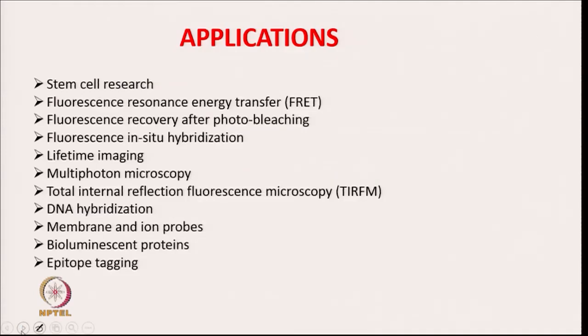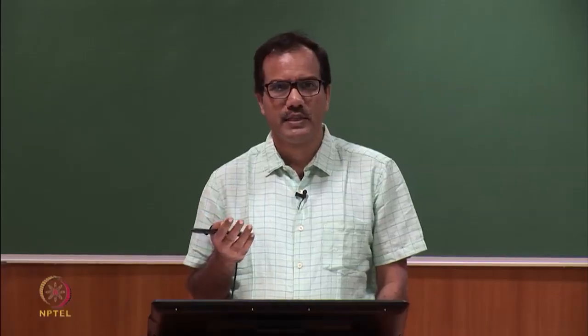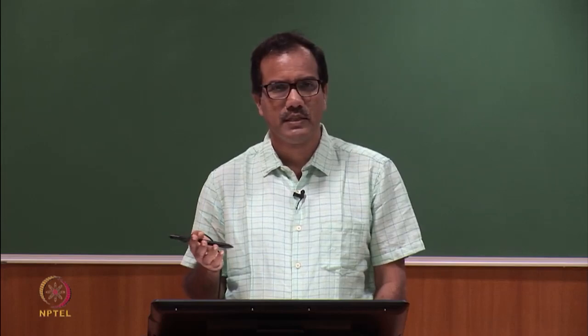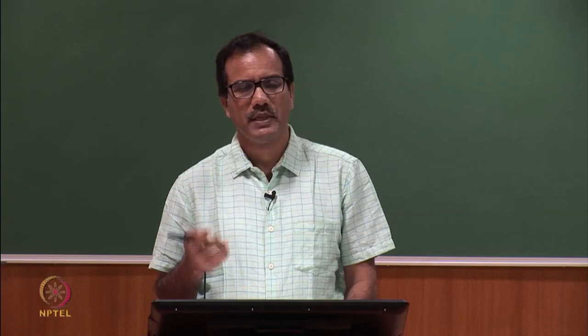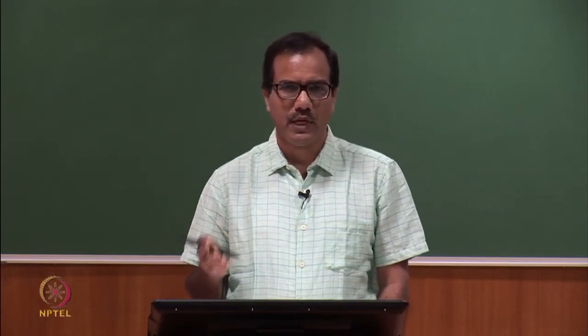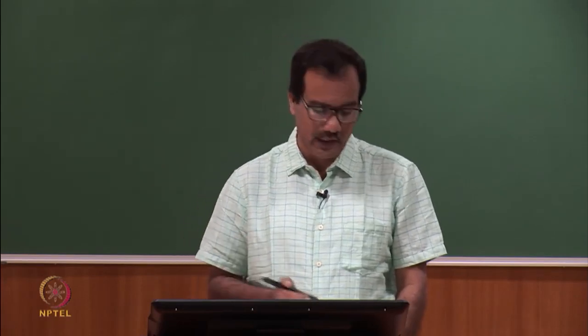In confocal microscopy, a laser light is focused onto a fluorescent specimen through the objective lens. The mixture of reflected and emitted light is captured by the same objective and sent to a dichroic mirror. The reflected light is deviated by the mirror while the emitted fluorescent light passes through the confocal aperture to reduce out-of-focus light; the focused light then passes through an emission filter to the photomultiplier tube. To generate an entire image, the single point is scanned in an XY manner as the laser focus is moved over the specimen. There are many applications of confocal microscopy including stem cell research, FRET interaction studies, fluorescence recovery after photobleaching, in-situ hybridization, lifetime imaging, multi-photon microscopy, and TIRF microscopy.